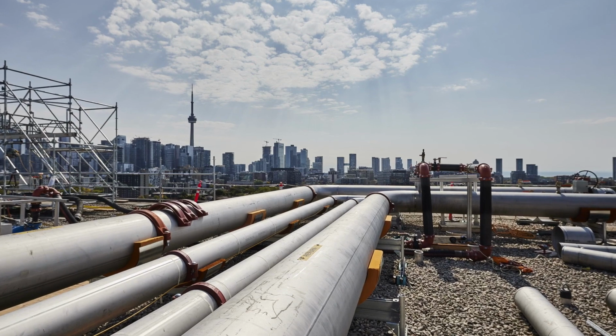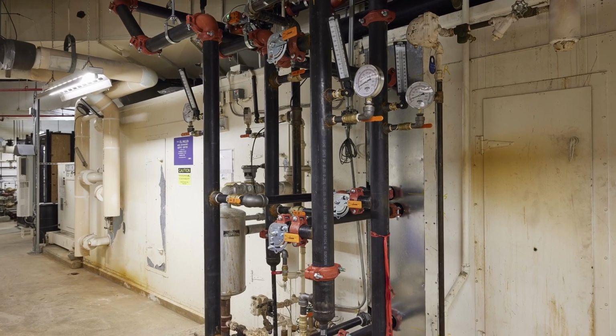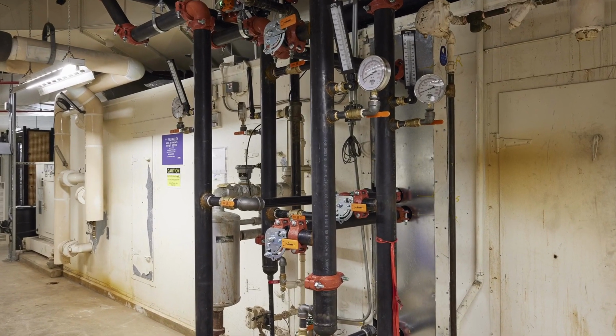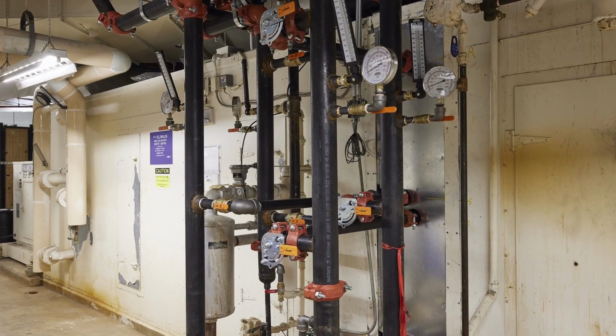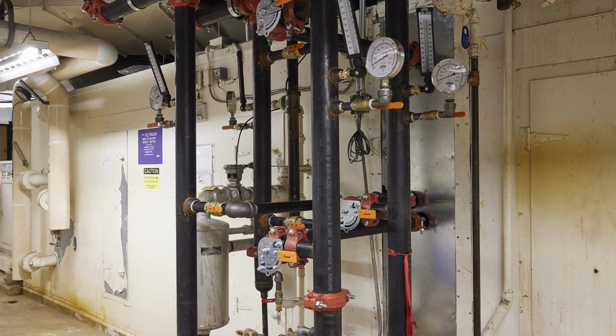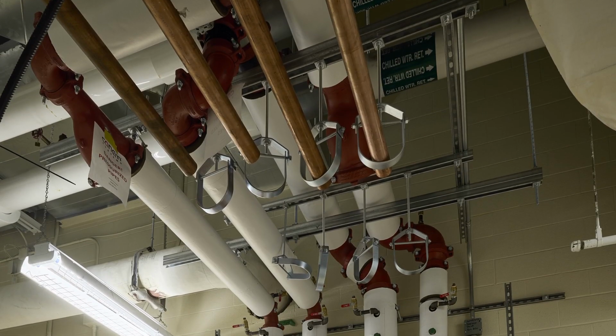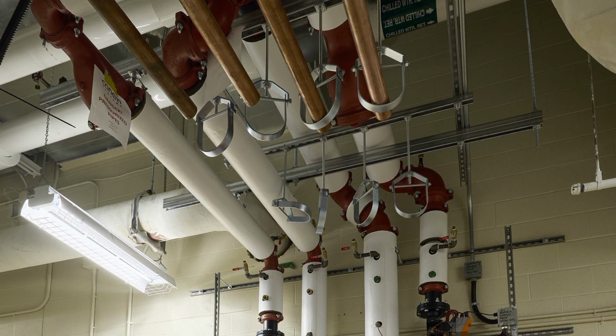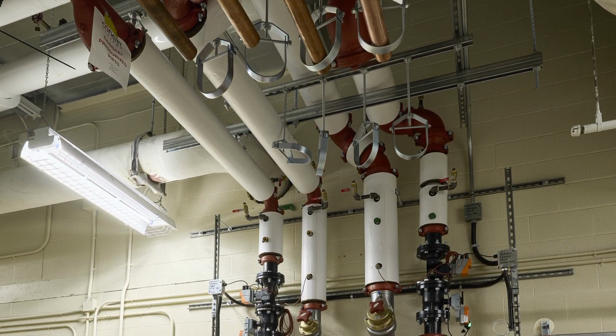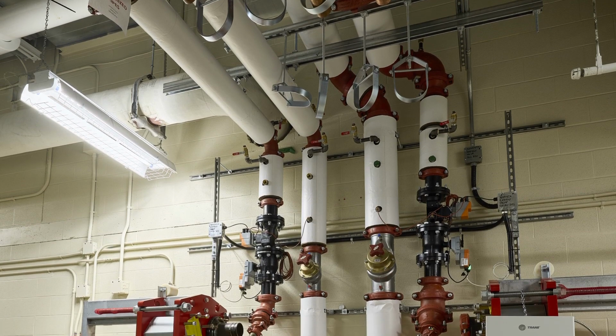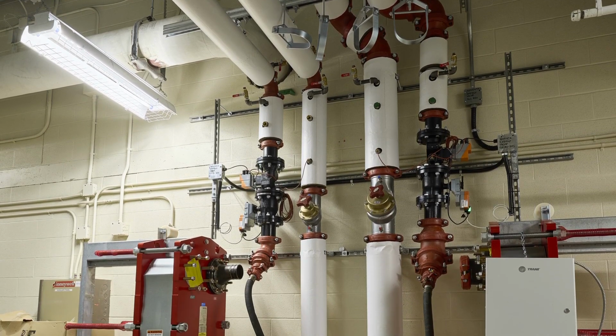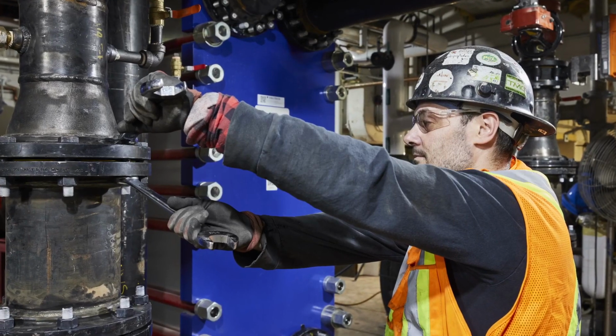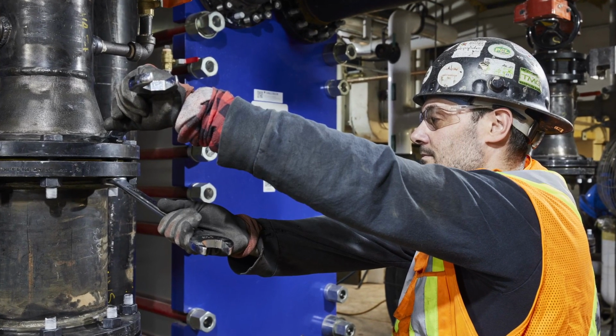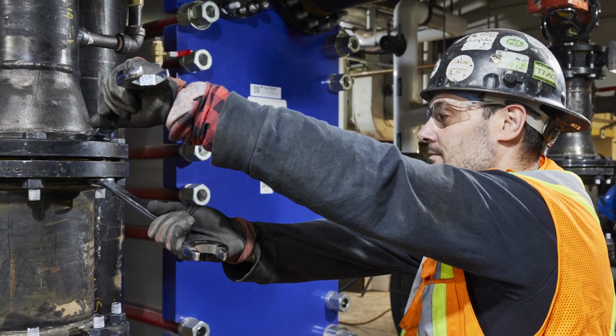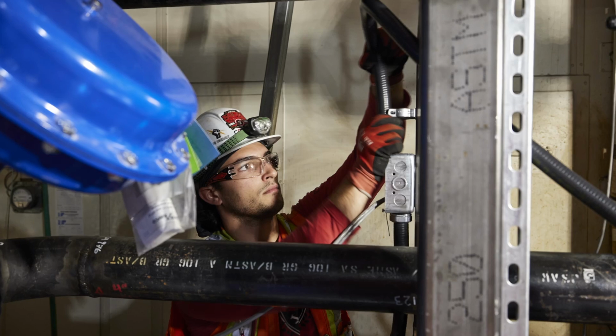Working with the hospital team also posed challenges. Since the hospital is in operation, our team was required to work around the hospital's schedule, planning any required work that would potentially impact the hospital to happen in the off hours, and requiring coordination with the hospital staff. The tight budget in this project also presented additional challenges, and value engineering became a large focus. Because of our early involvement, we were able to reduce the amount of redundant equipment and adjust the system design to remove 26 pumps and 13 heat exchangers.